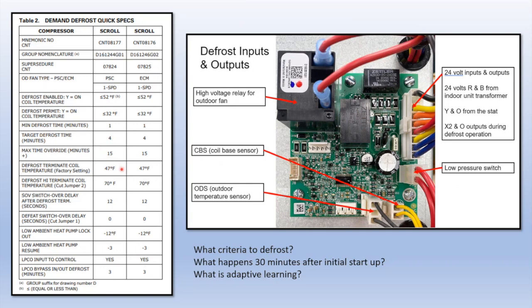The defrost termination temperature, so this is the temperature that the coil gets to before it says that the defrost is over, factory is 47 Fahrenheit. And the high termination, if you were to cut this jumper, is 70 Fahrenheit. The switchover relay valve delay is 12 seconds. So that means that the outdoor fan, when a defrost is about to finish, is going to turn on for 12 seconds before the switchover valve puts it back into heating mode. That's to drop that head pressure that rises during a defrost. And if you were to cut this jumper that says soft SW, now that switchover delay would go to 0 seconds, where the fan and the switchover would happen at the same time.